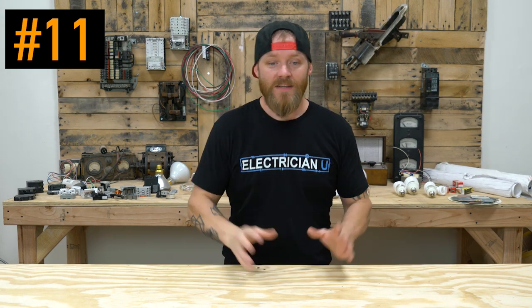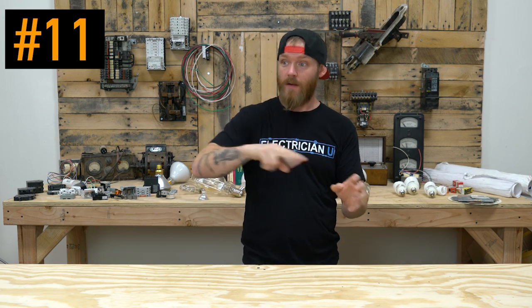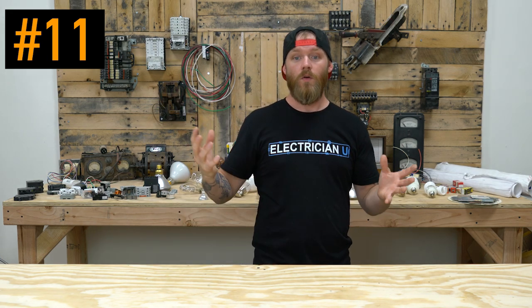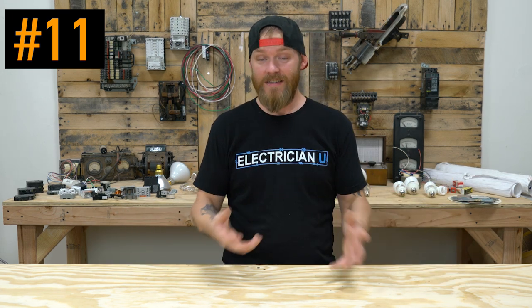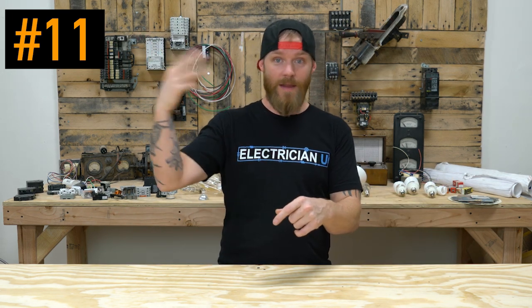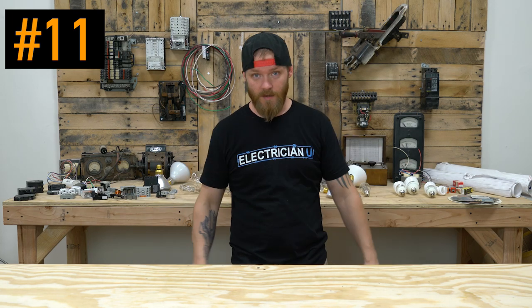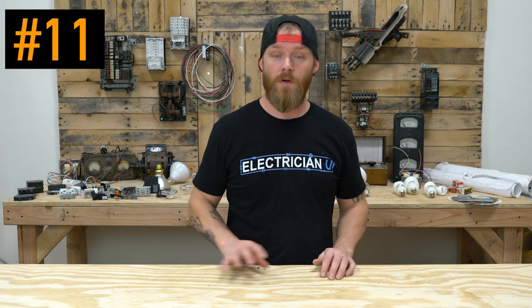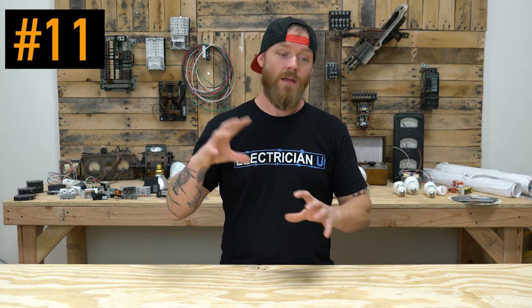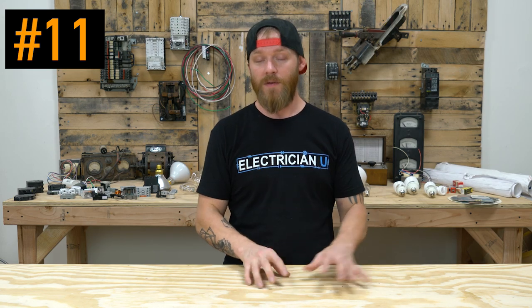And last, number 11 is disconnecting means. So disconnecting means basically is just a way to take a load, some piece of equipment, and disconnect the conductors that are feeding it from power. So basically a light switch is a disconnecting means for the light bulb. The light bulb has conductors going to it. You turn that switch off, now those conductors don't have any more current on them. So disconnecting means applies to a lot of things. You're going to see disconnecting means all over the code book in every piece of equipment, every environment. There are specific things that matter with the disconnecting means.